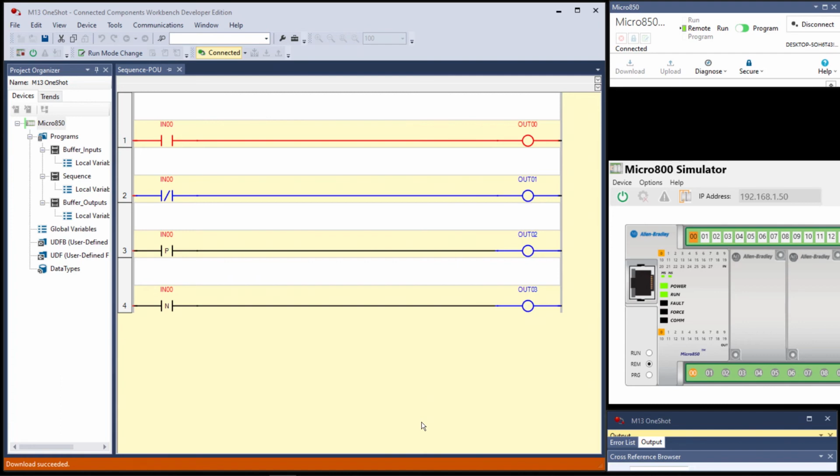Rung 1 is true, rung 2 is false, rung 3 is false, and rung 4 is false. Now, you say, well, they're not blue. Well, they're black, and those are one-shot instructions, and those instructions would only be true for one program scan, which is long gone by. By looking at the image on your computer, these 4 rungs list 2 elements that allow you to discern the on-off state of input 0.